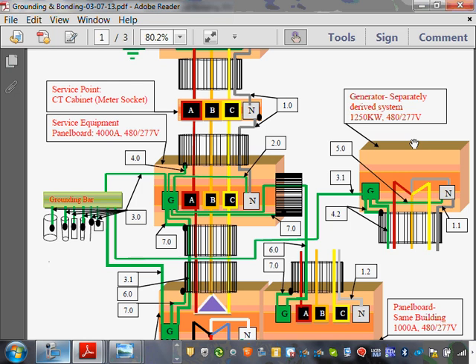So the scenario that I have right now here, guys, is, well, there's always an exception. The scenario that I have is for a separately derived system. So when we have a separately derived system, this generator is running as a separately derived system. So when I switch it, what do I have to switch? All 4. The 3 phases and the neutral.